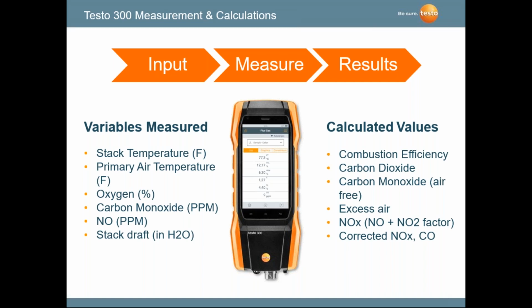We're calculating carbon dioxide. Certainly the difference between carbon dioxide and carbon monoxide, everyone should know. Carbon dioxide is a byproduct of combustion. We're going to have carbon dioxide in our flue gases, whereas carbon monoxide, or CO, we want to minimize in the flue gases. Excess air is calculated. Like I indicated in the previous slide, for NOx we're measuring NO and factoring in the NO2. And we're also correcting for NOx and CO at certain levels of oxygen.